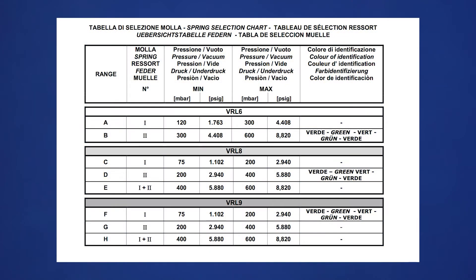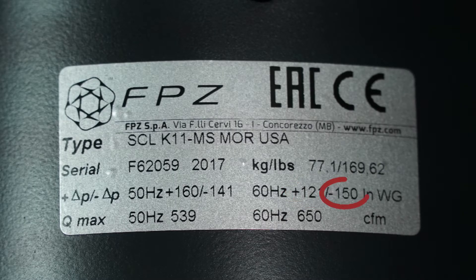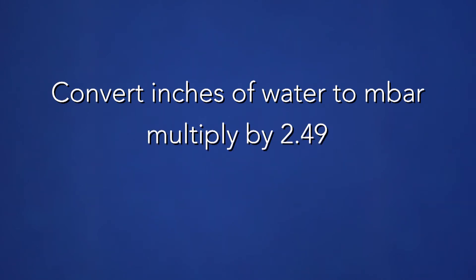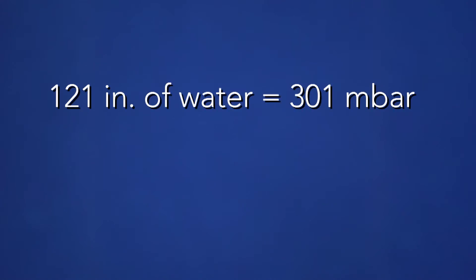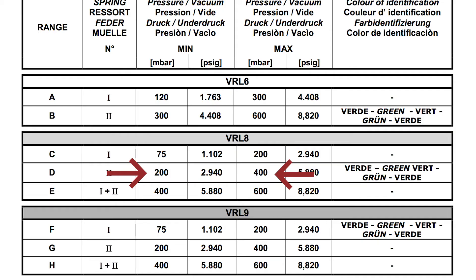The safety valve chart will list the pressure range for each spring combination. In our example, we are using the VRL-8 3-inch safety valve. The silver spring has a minimum set point of 75 millibar or 1.1 PSI and a maximum set point of 200 millibar or 2.9 PSI. The green spring has a minimum set point of 200 millibar or 2.9 PSI and a maximum set point of 400 millibar or 5.8 PSI. For pressure above 5.8 PSI, both springs are used. In our case, the set points are 121 inches of water for pressure or negative 150 inches of water for vacuum. We will convert inches of water to millibar by multiplying by 2.49. 121 inches of water equals 301 millibar and 150 inches of water equals 374 millibar, so we will use the green spring.